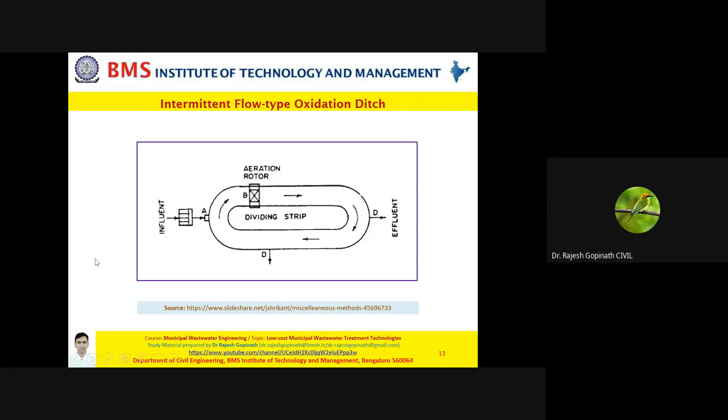Please note that this is not a continuous flow system. If you remember when I taught you sedimentation tank, I told you continuous flow, intermittent flow. So here the wastewater is allowed to enter. Once the wastewater enters the entire capacity, the influent is stopped, the effluent is stopped. And then the operation begins.